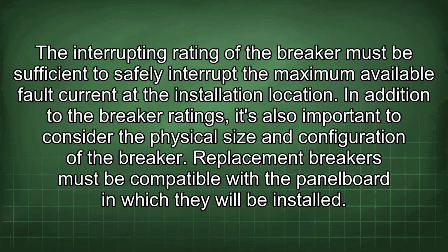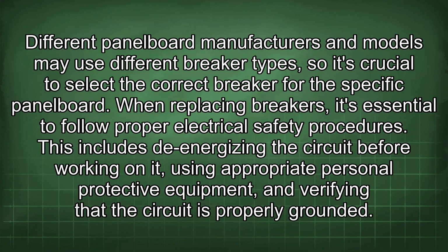In addition to the breaker ratings, it's also important to consider the physical size and configuration of the breaker. Replacement breakers must be compatible with the panel board in which they will be installed. Different panel board manufacturers and models may use different breaker types, so it's crucial to select the correct breaker for the specific panel board. When replacing breakers, it's essential to follow proper electrical safety procedures.